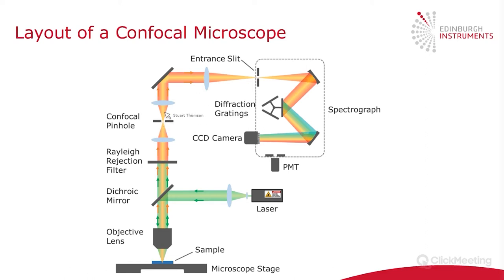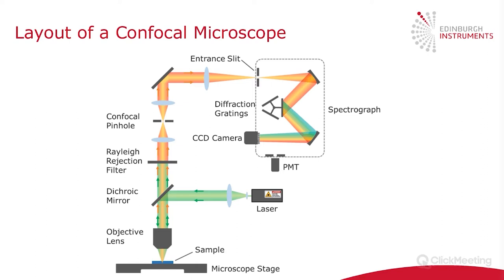The signal continues into the entrance slit of the spectrograph, which is used to wavelength-select the signal. The light is focused using a mirror onto a diffraction grating, which separates the light into its constituent wavelengths. This is usually a grating turret — on our Raman microscopes there are five grating turrets. For photoluminescence you'd use a low dispersion grating because you typically have very broad spectra, whereas for Raman microscopy you'd use a high groove density grating for the higher resolution required to analyze Raman peaks.